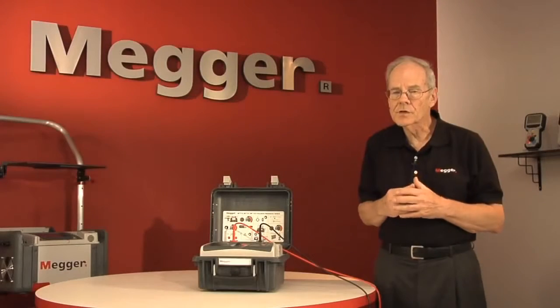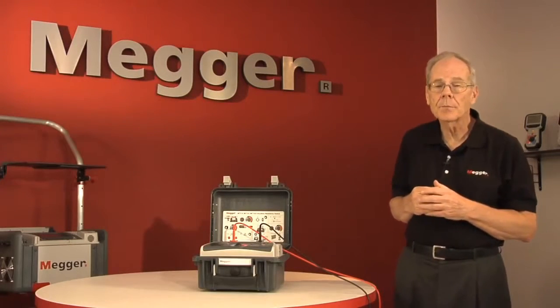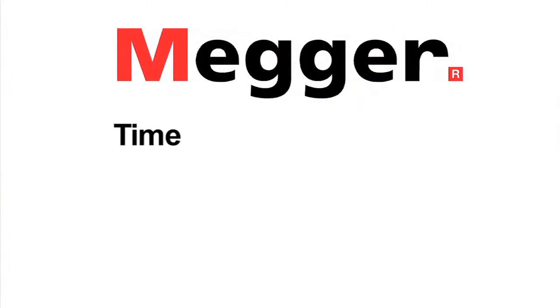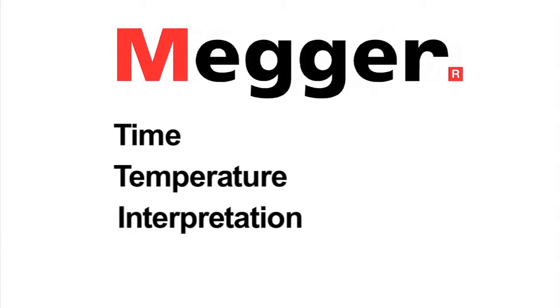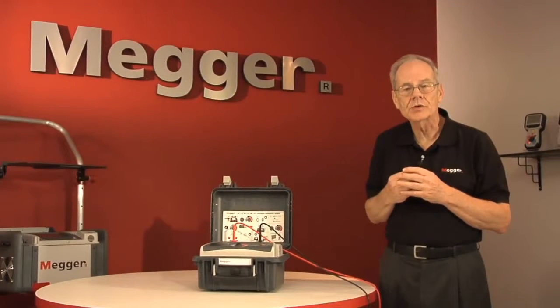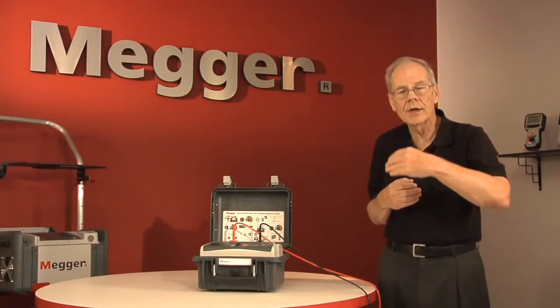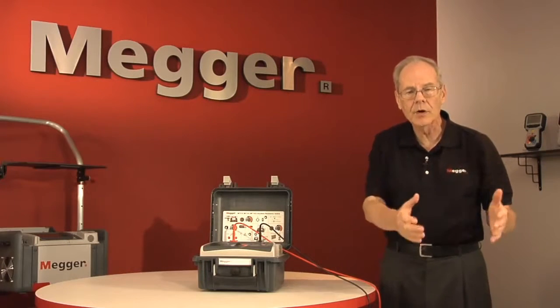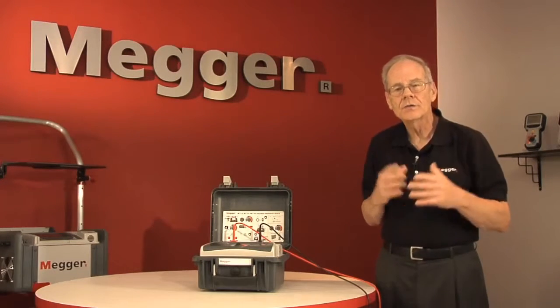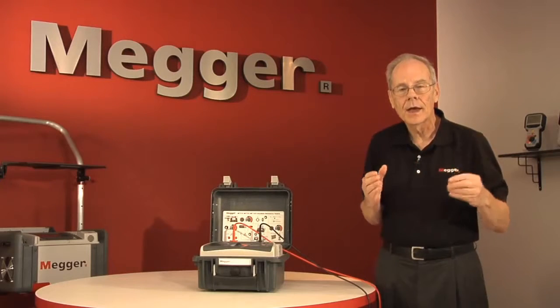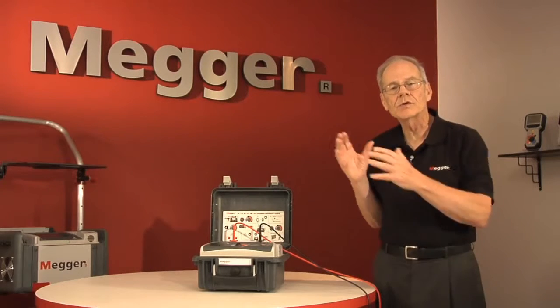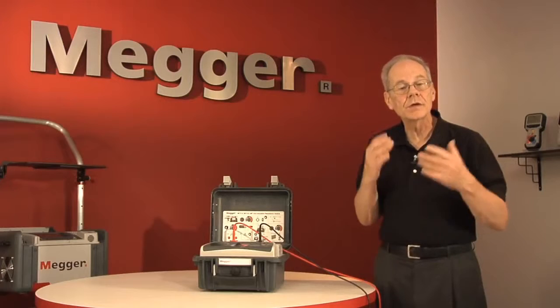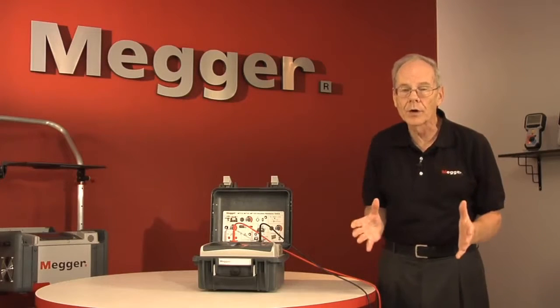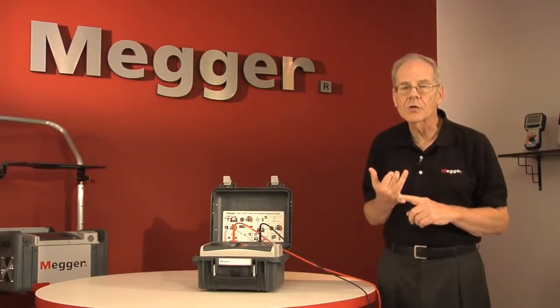The limitation of the spot reading test is that it's dependent upon time, temperature, and interpretation. Because the test item is charging and the readings are changing as the item goes to full charge, time is important, and the time at which the reading was taken influences the actual number that gets recorded. Temperature is also a factor.